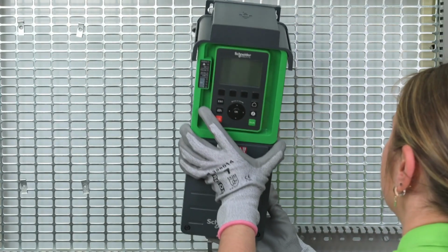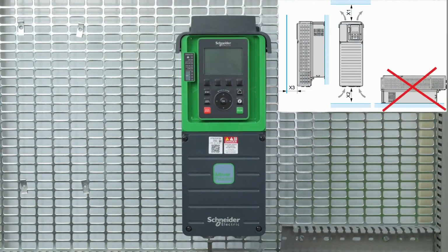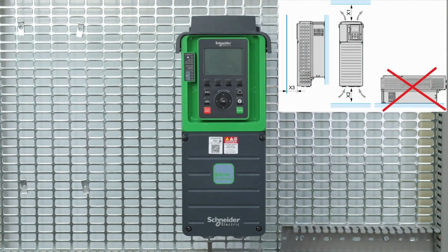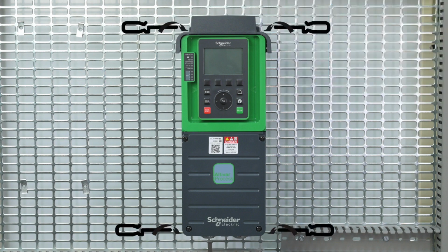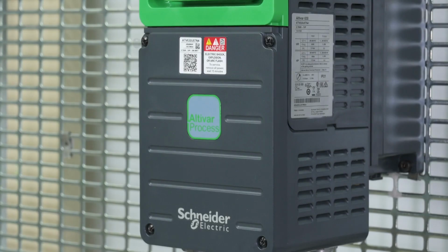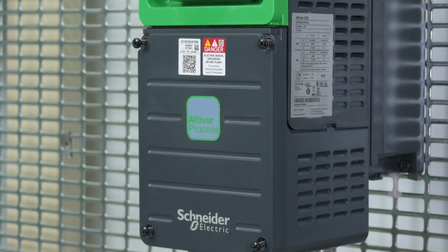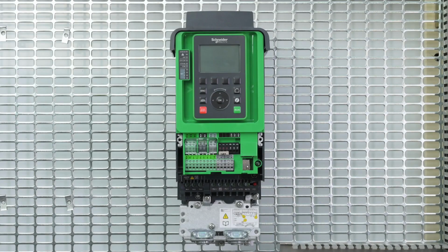Install your ATV600. The product has to be mounted vertically as shown in the Getting Started, along with other mechanical and environmental constraints. The drive is designed to be used in a controlled indoor environment. Tighten the 4 fixation screws in each corner of your product. Let's start the wiring by removing the cover located under the control block by unscrewing the 4 captive screws.